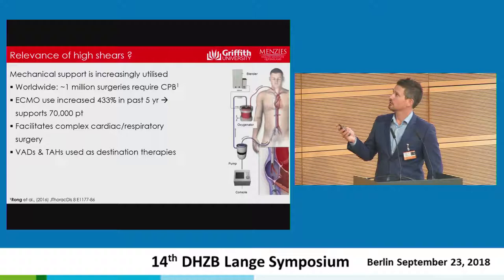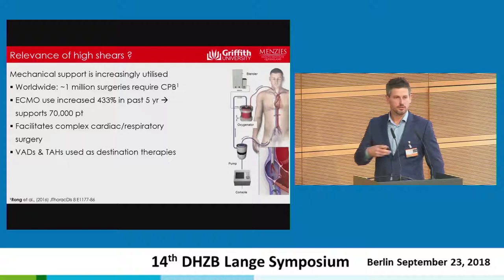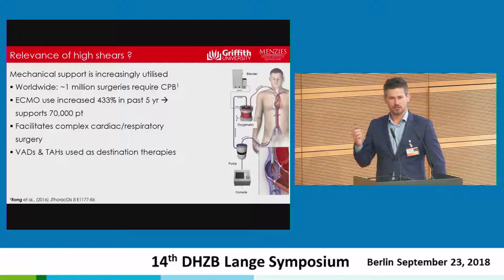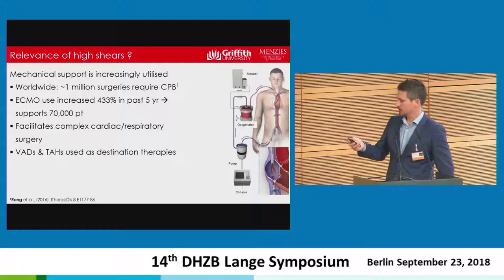Why study high shears? In isolation of mechanical support, people might ask why explore supraphysiological shear stress. Well, circulatory support is used in all sorts of cardiothoracic interventions — around one million surgeries each year require these devices. These devices have blood pumps and oxygenators which are very high shear regions: anywhere in the order of 150 to 250 Pascal being induced on the fluid. In contrast, our own blood is only ever exposed to about 10 to 15 Pascal in vivo. This is a really unusual and artificial environment.